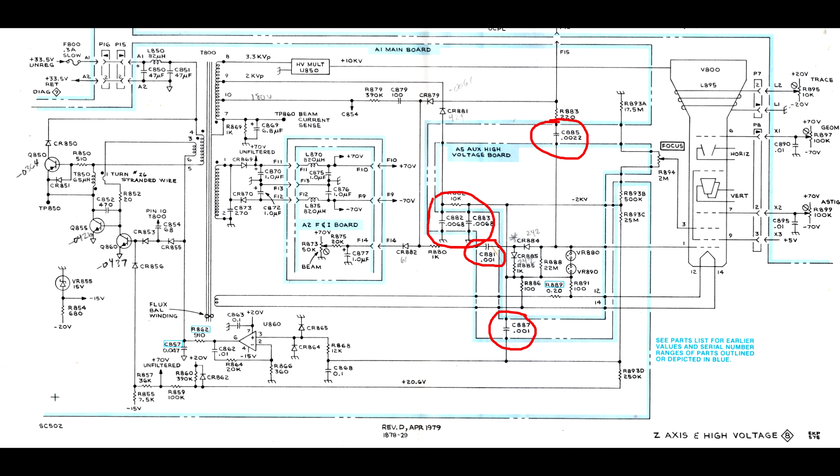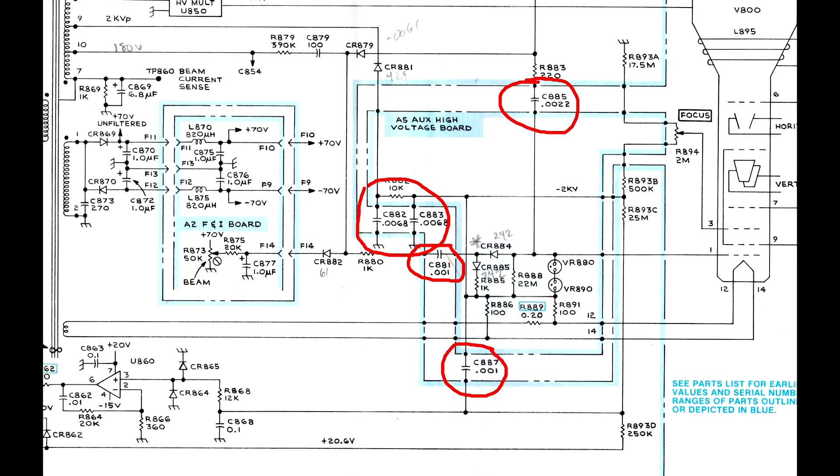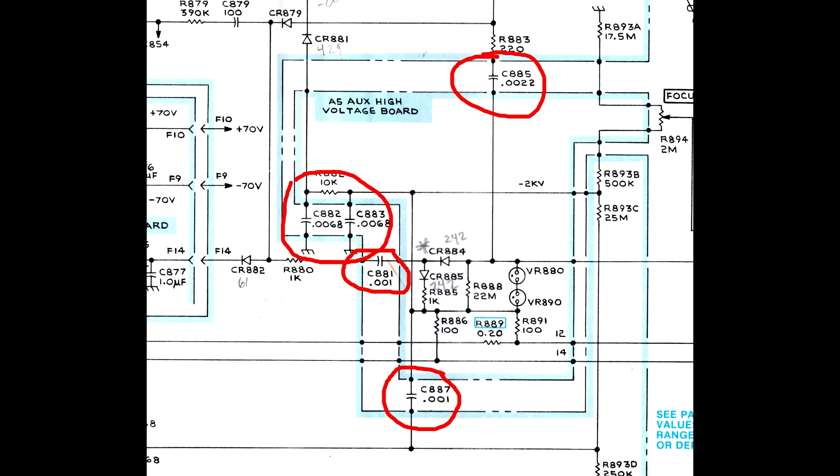While I was editing this video, the topic of intensity control problems on the SC502 has shown up on Tekscope's group. I find that I had a problem with that on an SC502 and the problem was the one or more of the five capacitors in the DC restore circuit, which are outlined here.